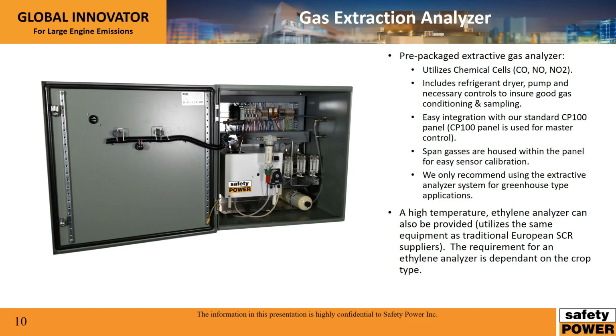It is easily integrated with our standard CP100 control panel, but it interacts primarily with the damper valve. Basically, it takes CO, NO, and NO2 measurements within the greenhouse and before the greenhouse, and then, depending on what it measures, the bypass valve will either be opened or closed. The CP100 panel controls the emissions, the NOx out and everything, separately. Calibration gases are also housed within the panel for easy sensor calibration, and that's just for convenience.